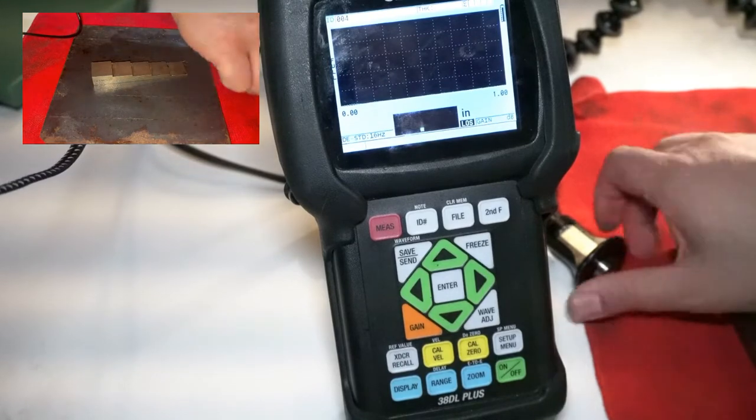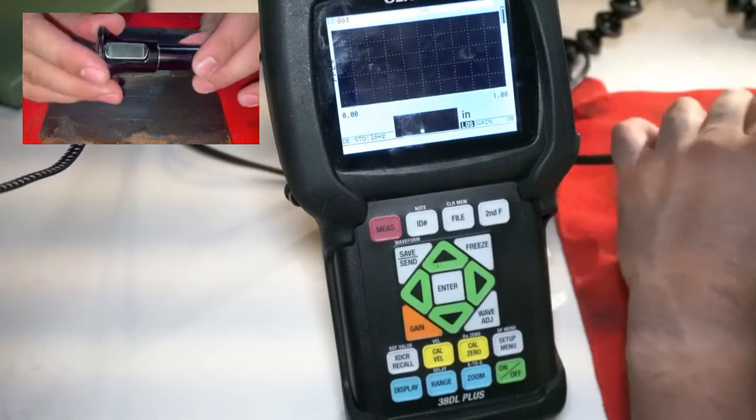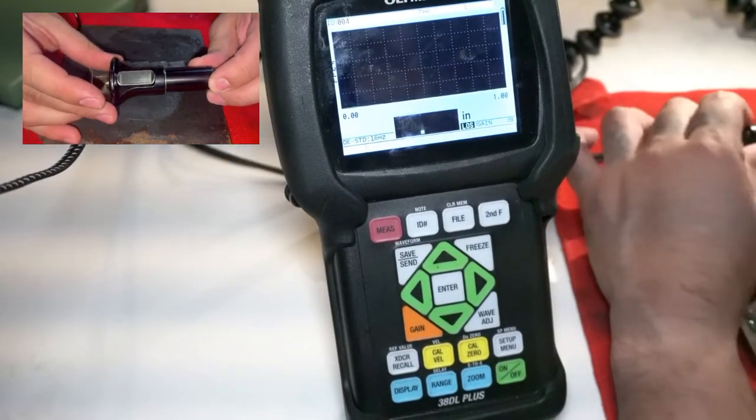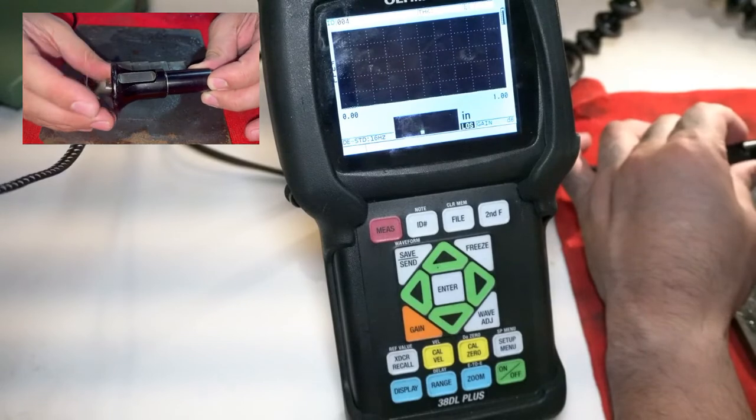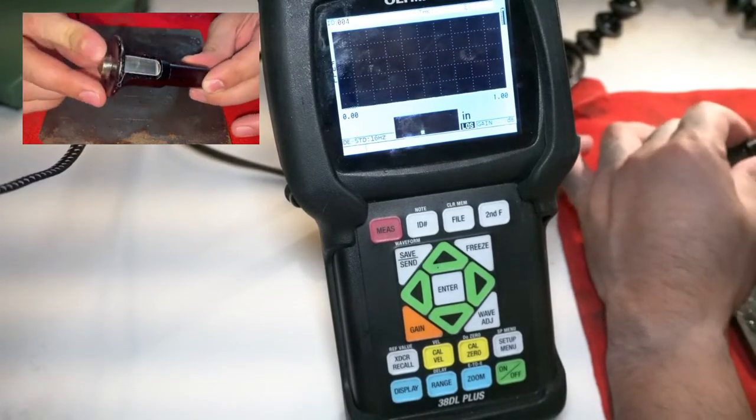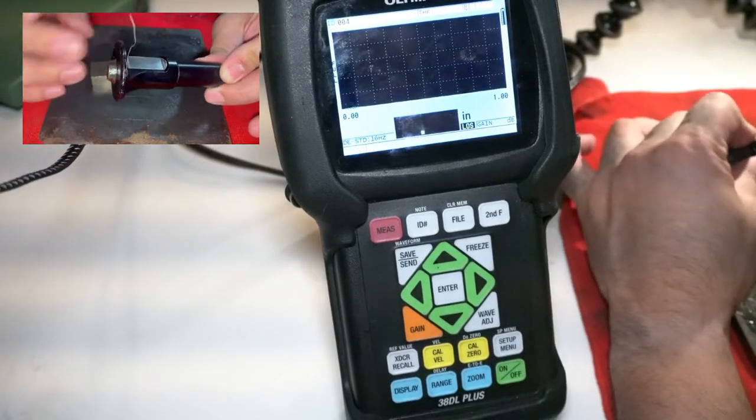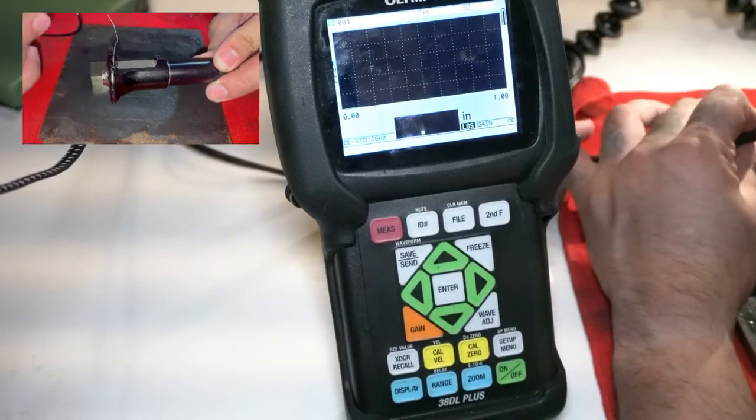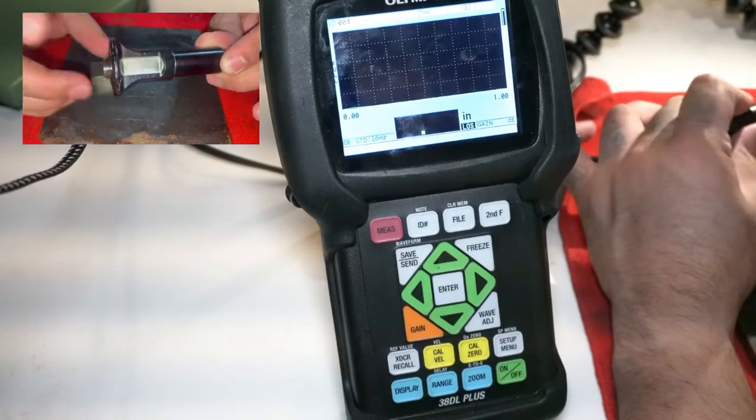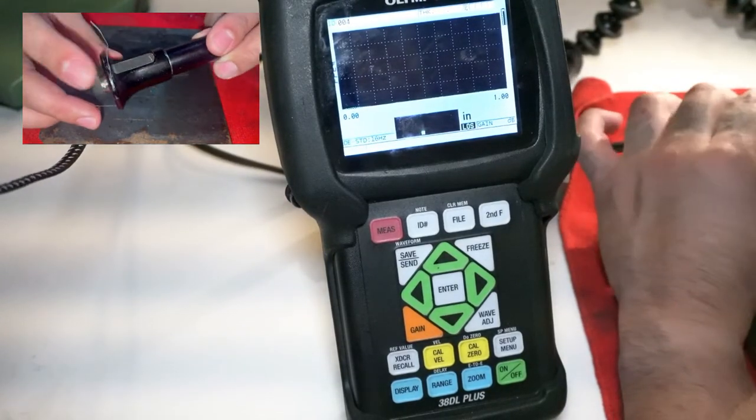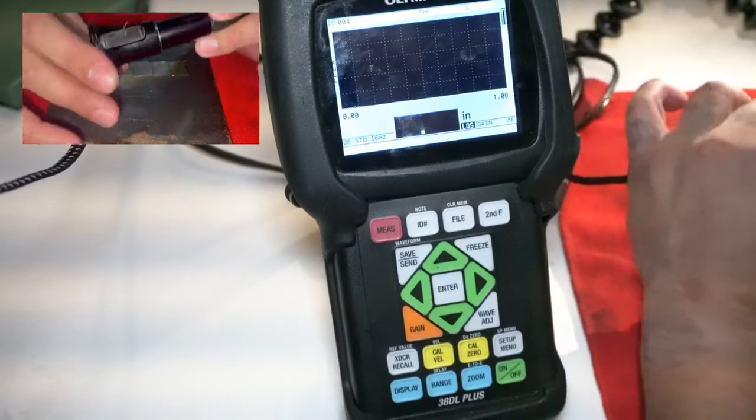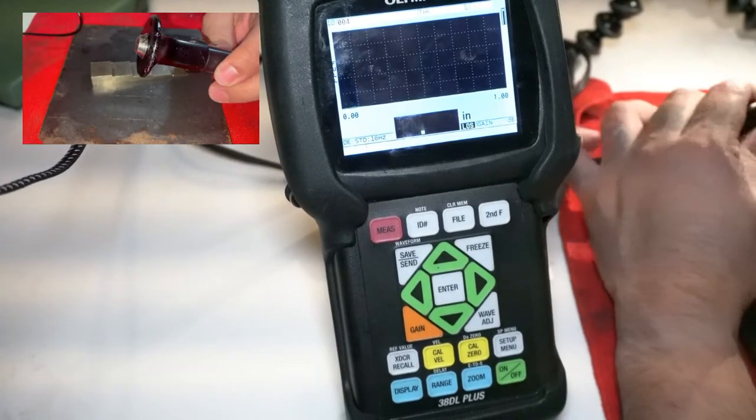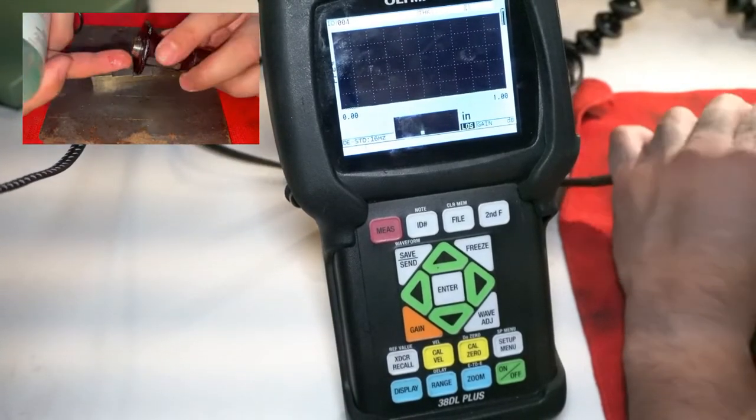I am using a D790, a five megahertz transducer pretty typical for what we use in the petrochemical industry. I'm gonna go ahead and leave this on. It really helps out well when scanning plates and pipe. Great for ergonomics, right? That's the reason for the design.